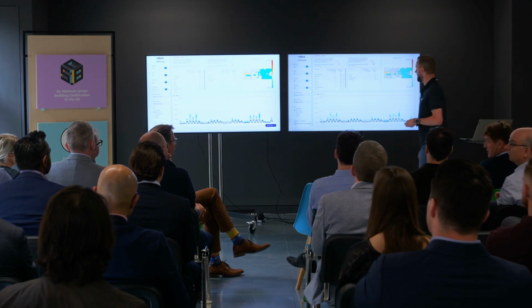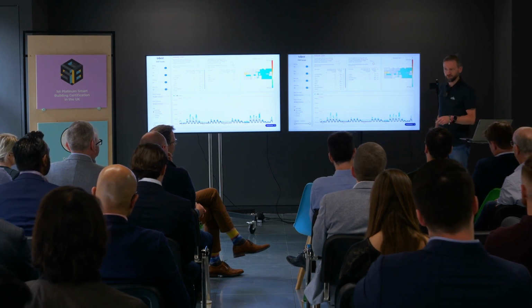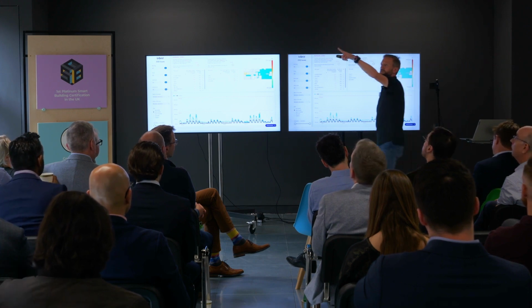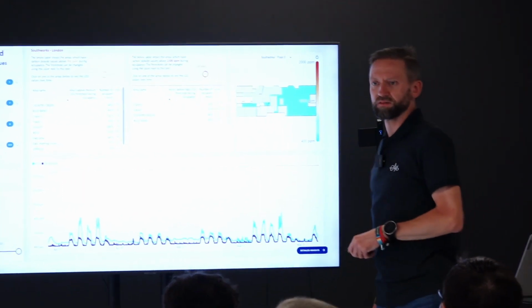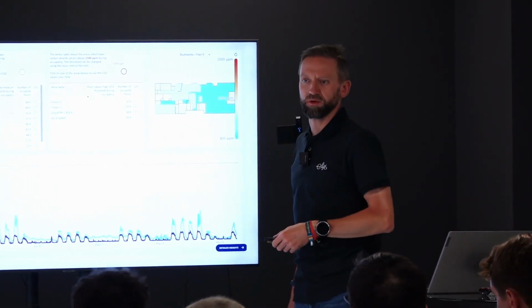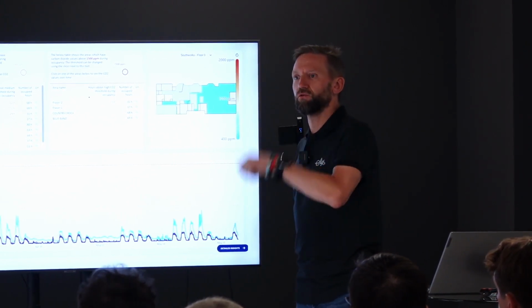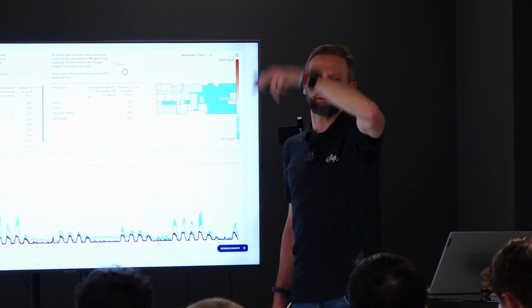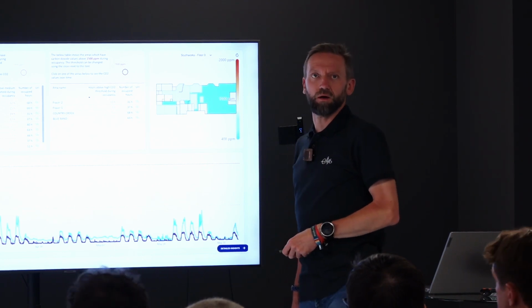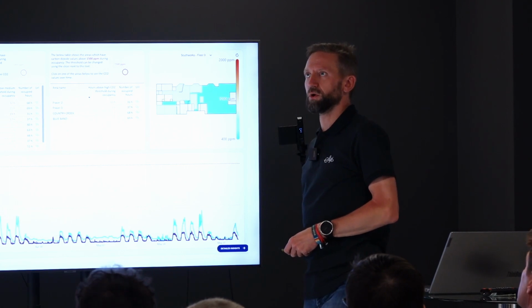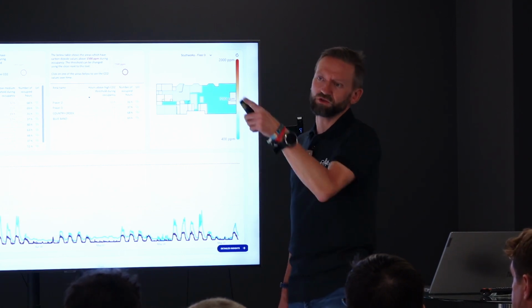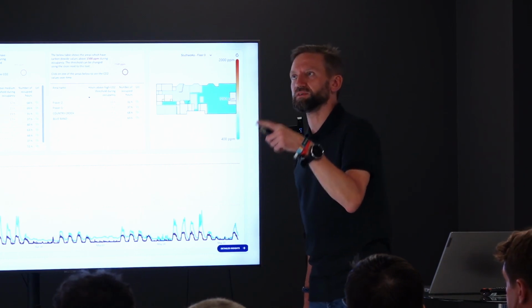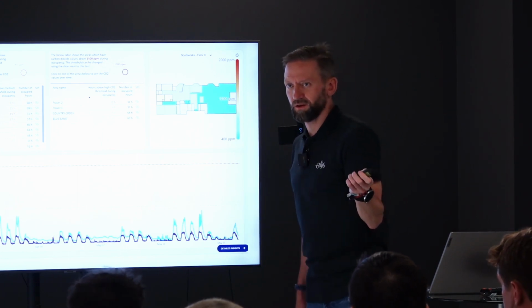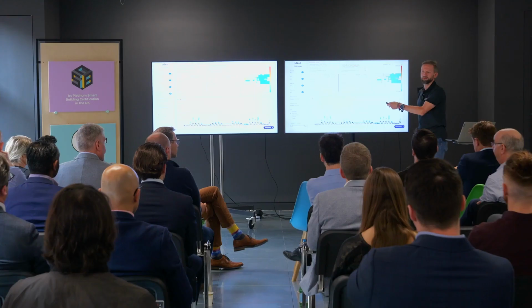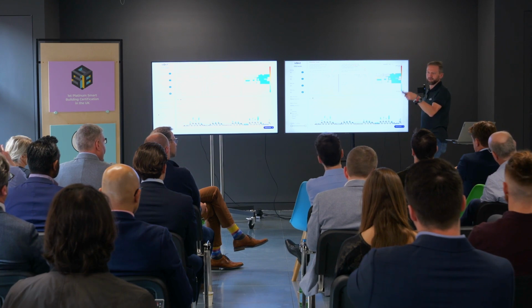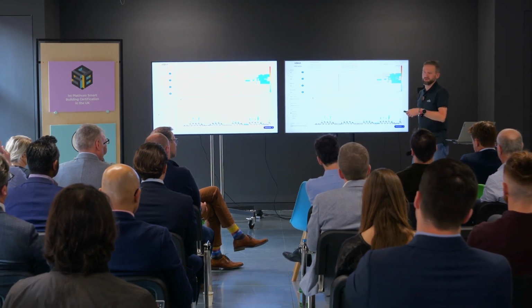It's the sensor. The guys from bGrid will tell you much more, but the PIR sensor, the small bubble, will tell you if there's movement in the space, and bGrid also, but it won't usually tell you how many people are there. You'd use different technologies for that. We didn't go for those technologies because usually they're camera based, so they basically count heads. They're expensive, and usually people have privacy concerns. Usually there's no reason for you to know if there are 5 or 6 people somewhere. When you have a reason, you can just implement them. And this is great, because if someone wants it, we can buy such a sensor. It's not from bGrid, but there's a way to integrate this third-party sensor into the same network. This clever algorithm is able to estimate the number of people within the meeting room or space.